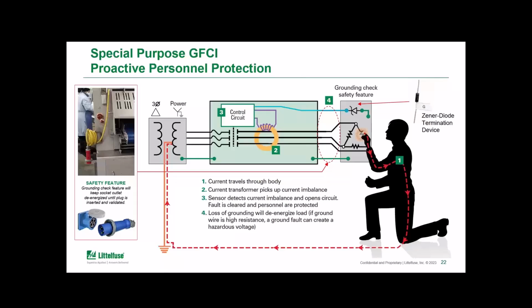Now, the Zener diode termination, just to avoid confusion here, is not a requirement of the UL 943 standard, but that particular termination is something that Littelfuse uses to allow the device to detect if there is a pilot to ground short somewhere in the cable.